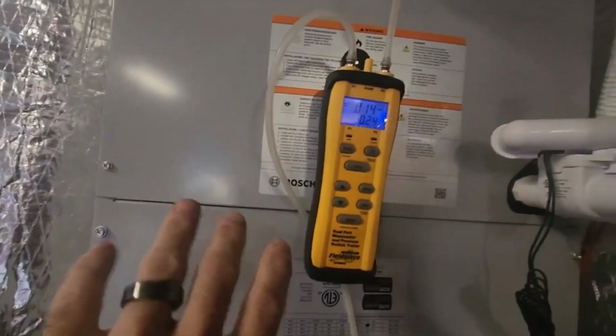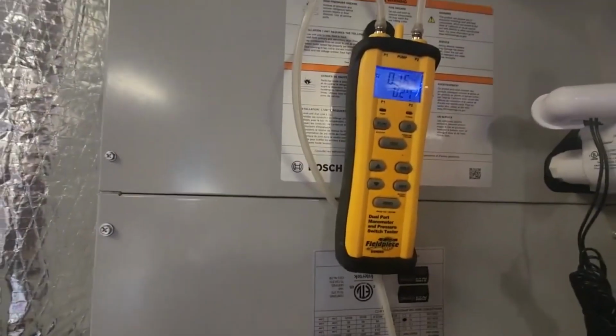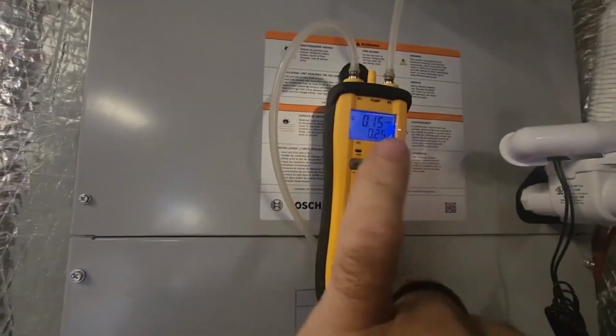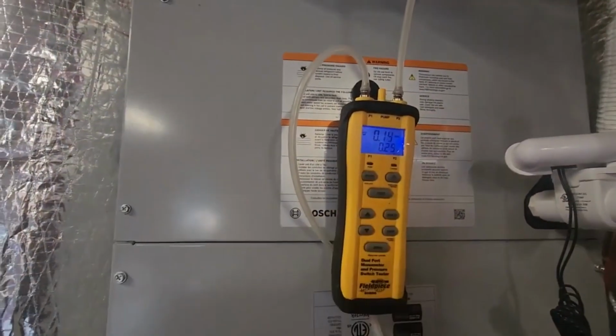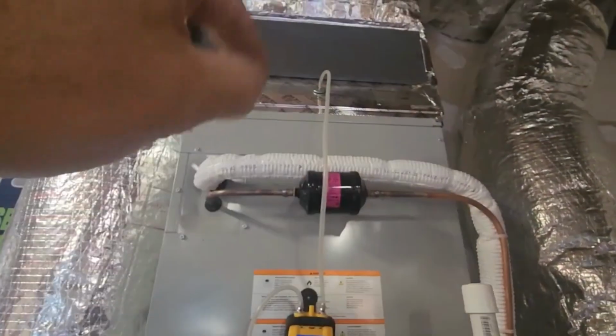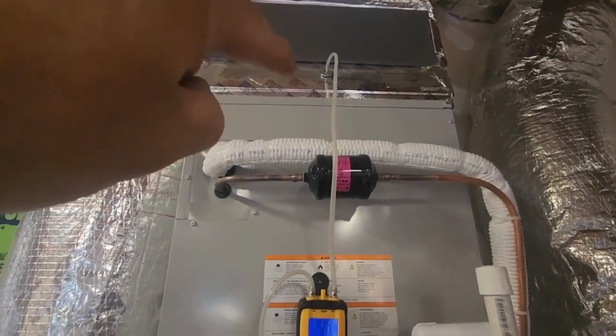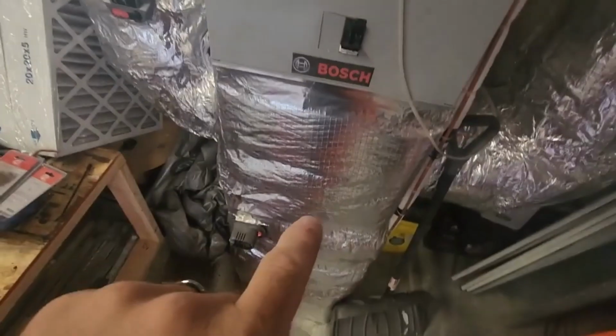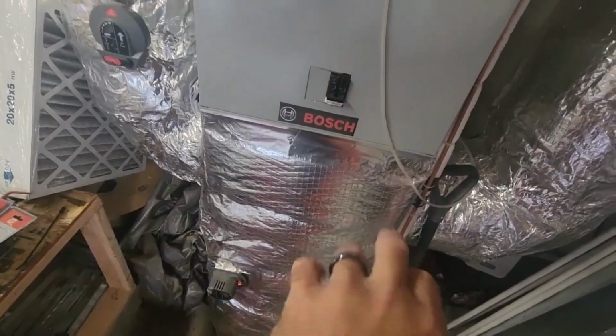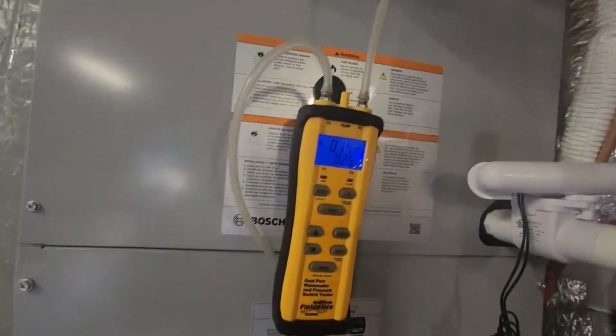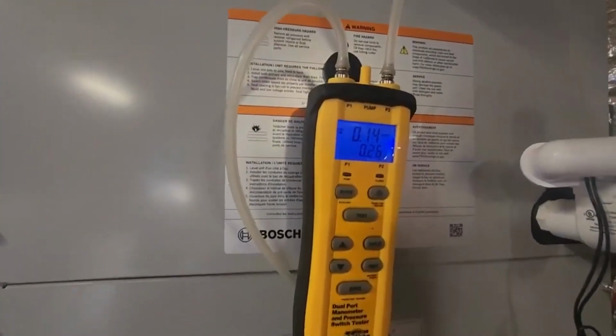Obviously, you guys, when you're doing a conventional system, you're just going to do your supply and return. I recommend taking your readings in a couple different spots, because it's going to vary a little bit. That's why these spacers are important on your return. You want to get between the filter and your air handling equipment. Then on these, do it in a couple different spots and take an average, and that'll get you pretty close to what your actual static pressure is.